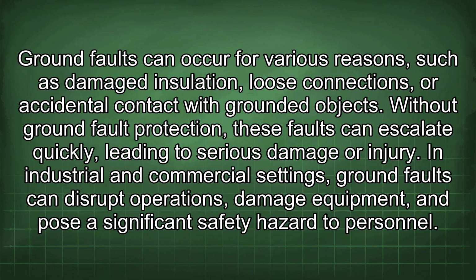Ground faults can occur for various reasons, such as damaged insulation, loose connections, or accidental contact with grounded objects. Without ground fault protection, these faults can escalate quickly, leading to serious damage or injury. In industrial and commercial settings, ground faults can disrupt operations, damage equipment, and pose a significant safety hazard to personnel.